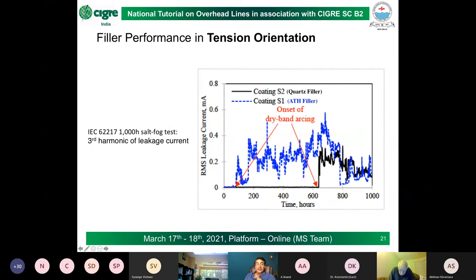Whereas on the ATH filled coating, the leakage current commences within under 50 hours. So this extra leakage current is really a bad thing. And if anyone is ever considering using a coating on a tension insulator, this is a key parameter to look at, because you do not want your leakage current to start really quickly within 2 days of onset. So this is a good test here.